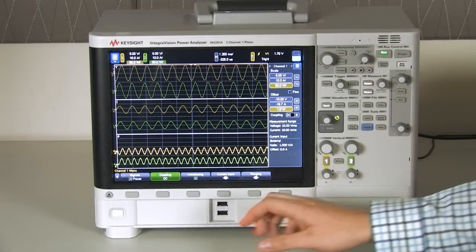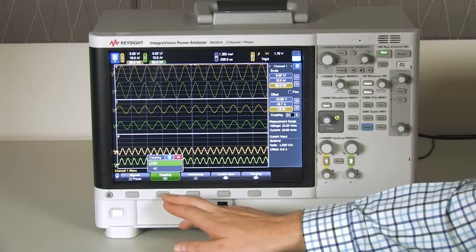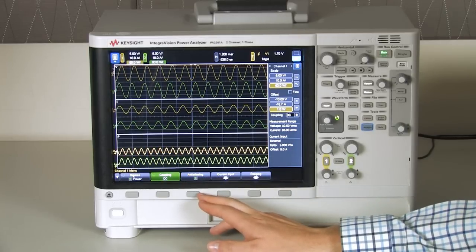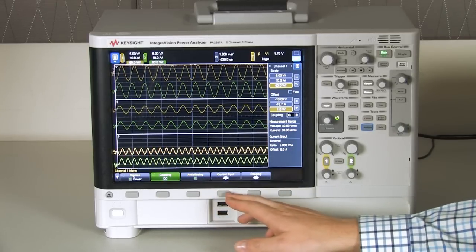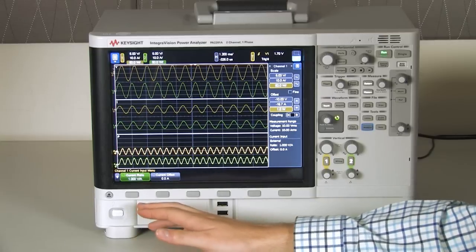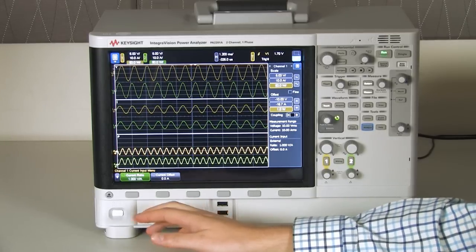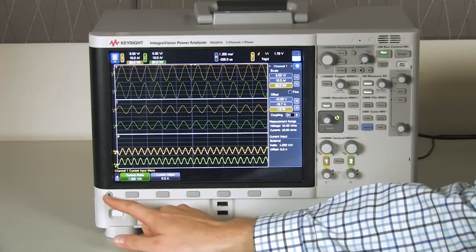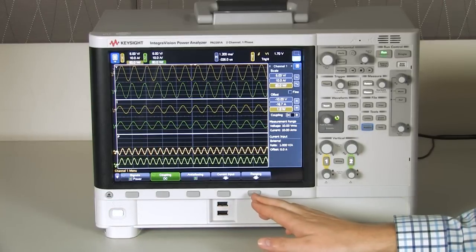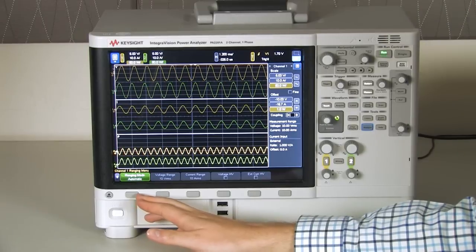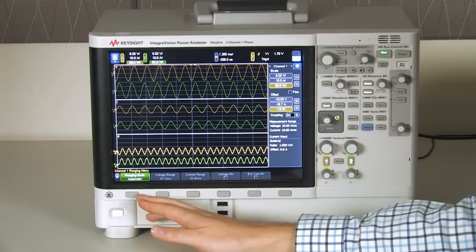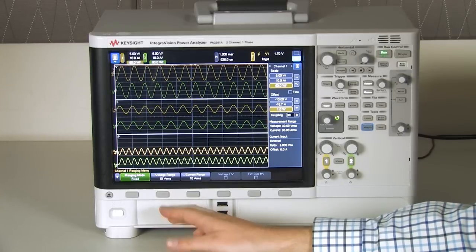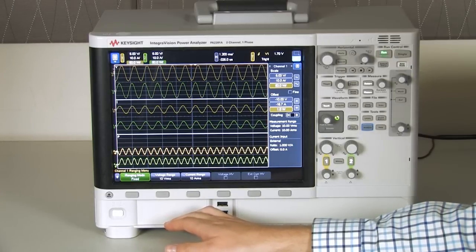If we go into channel 1 here, we can change the coupling to be either AC or DC coupling, enable or disable anti-aliasing, and we can have control of the current inputs. If we have a current probe hooked up, we can set the ratio and the offset for our probe. The last major control we have under the channel menu is ranging. We have either automatic or fixed ranging. Fixed ranging is best when you're trying to capture small transient events that may not be picked up by automatic ranging.